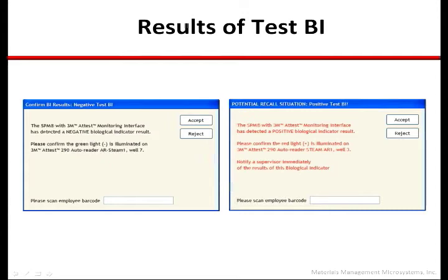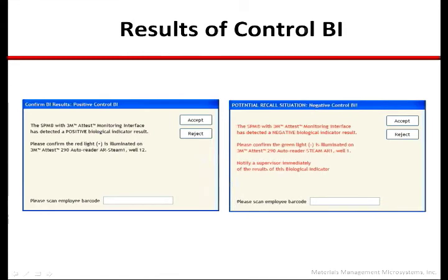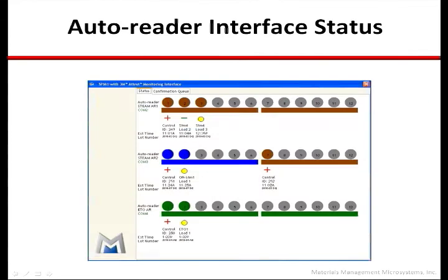These are the two screens for advising the technician to confirm the outcome of the test BI. The first is the negative result, asking for the technician to visually confirm the result that the auto-reader and interface have provided. The second is the positive result, where the same confirmation is required and where the recall sequence would then follow. These are the two screens for advising the technician to confirm the outcome of the control BI the auto-reader has incubated. The first screenshot is an example of a positive control BI asking for the technician to visually confirm the result. The second screenshot is an example of a negative control BI result where the same confirmation is required and a supervisor should be consulted to determine next steps.